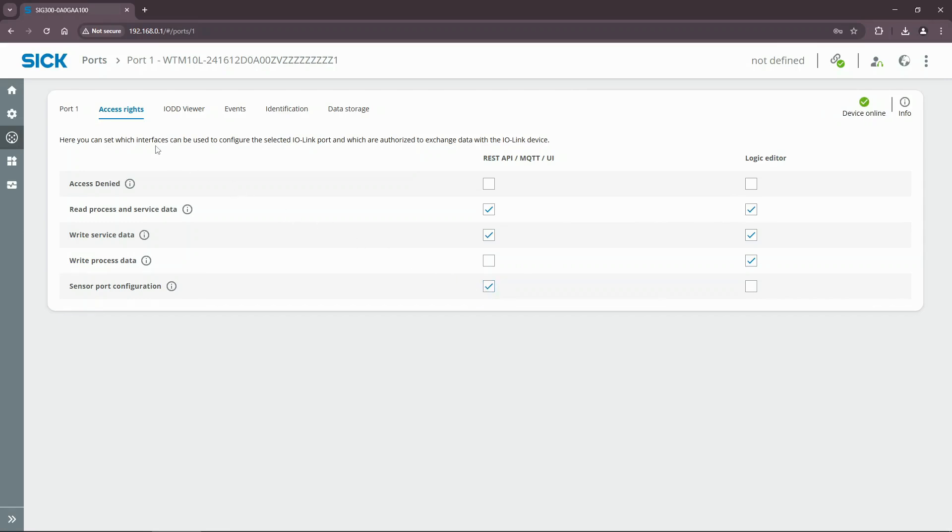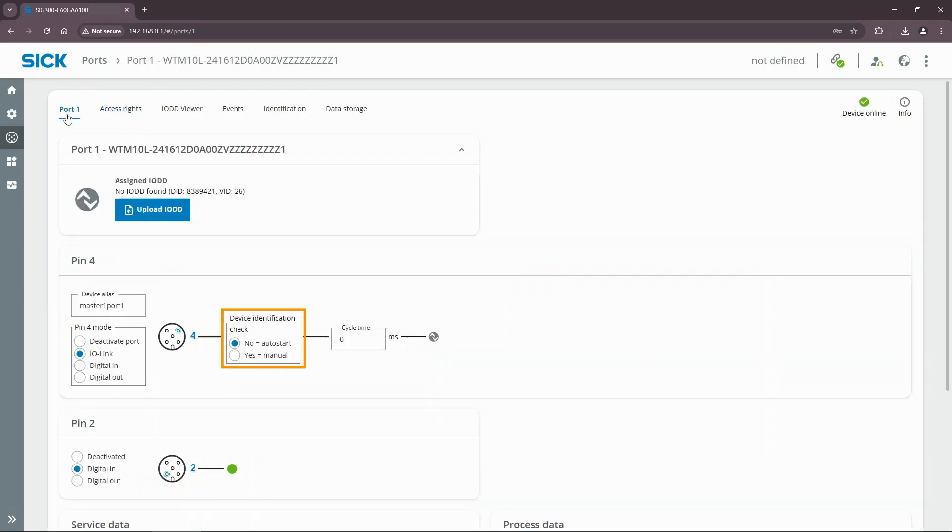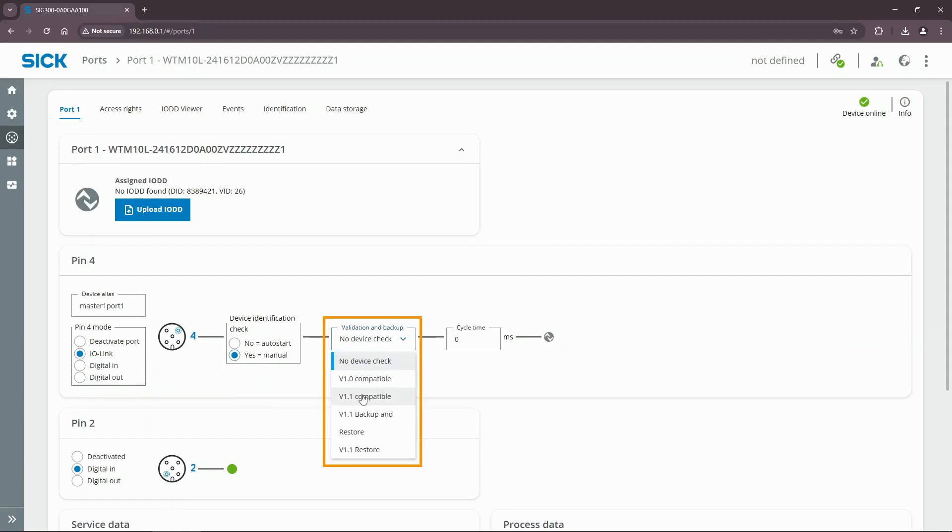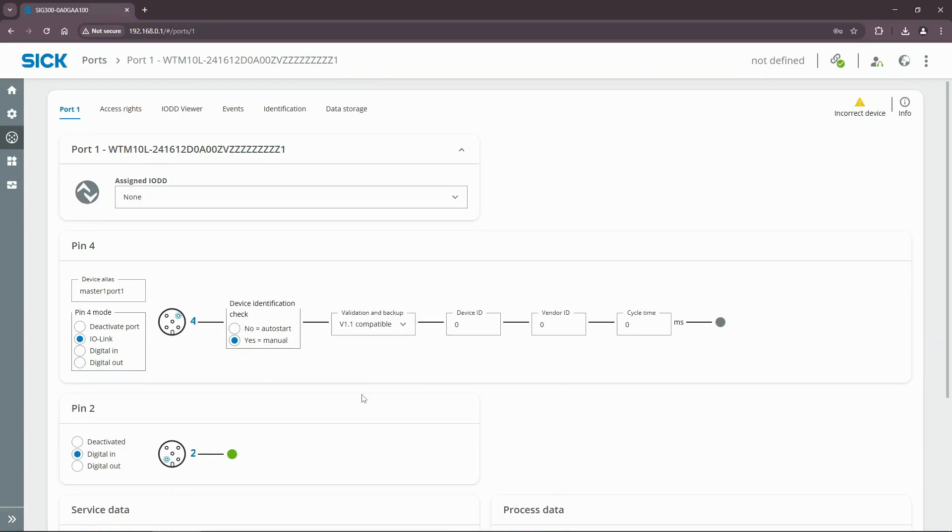Open the port 1 settings again. It is important to set a manual device identification mode to have the WTM10 inputs available in the logic editor. So let's set the device identification check to manual mode. Set the validation and backup mode to device version 1.1 since the WTM10 supports IO-Link standard version 1.1. Make sure to select the correct IODD file.